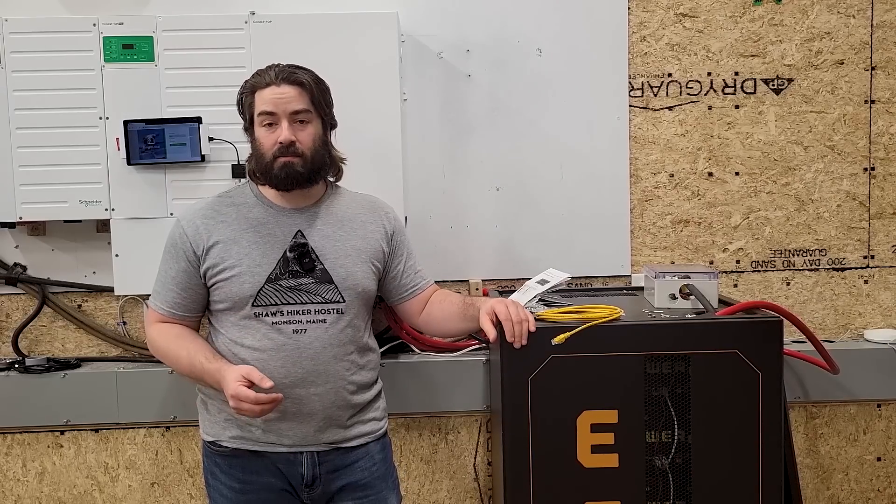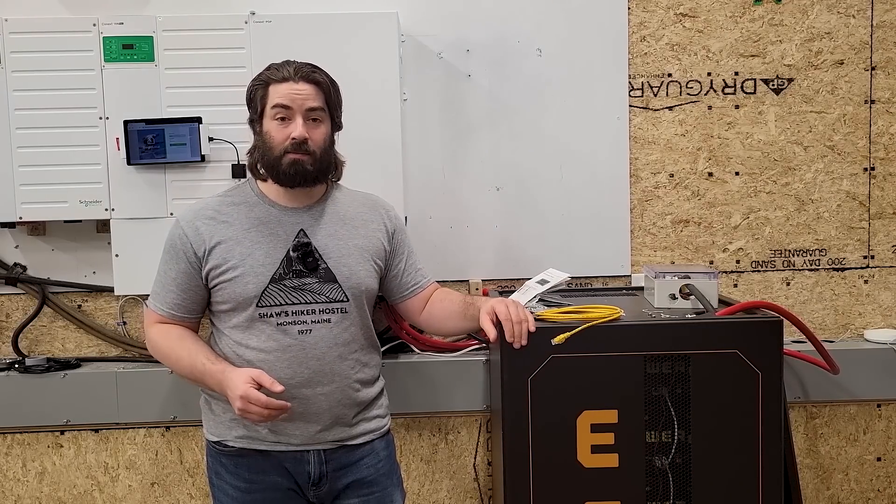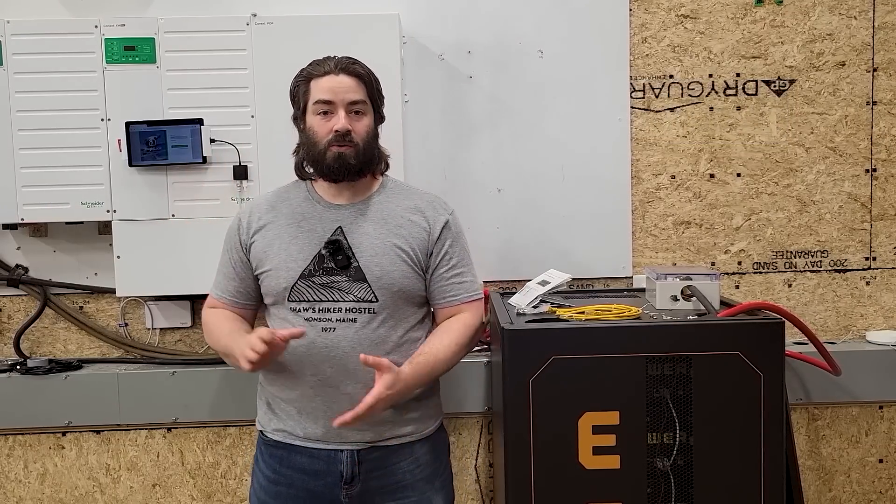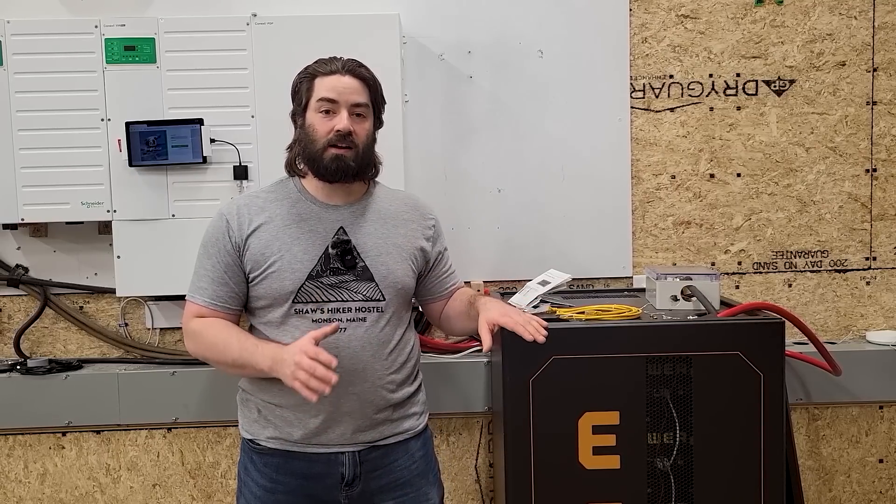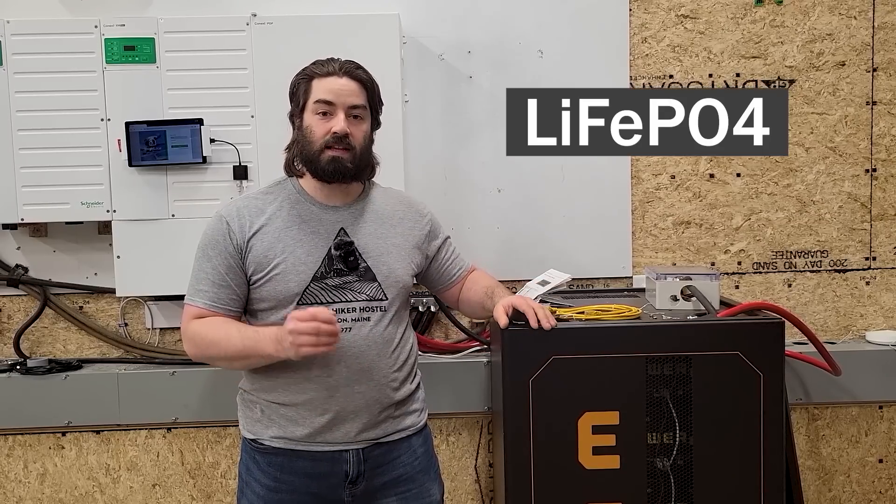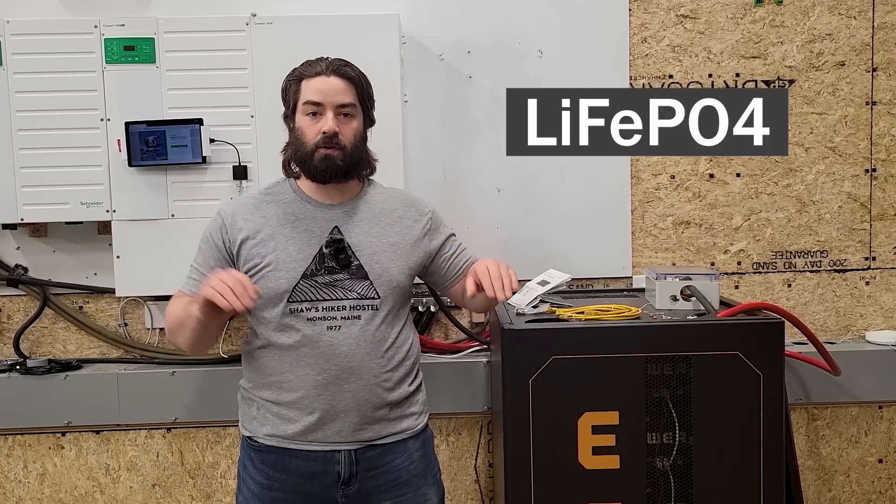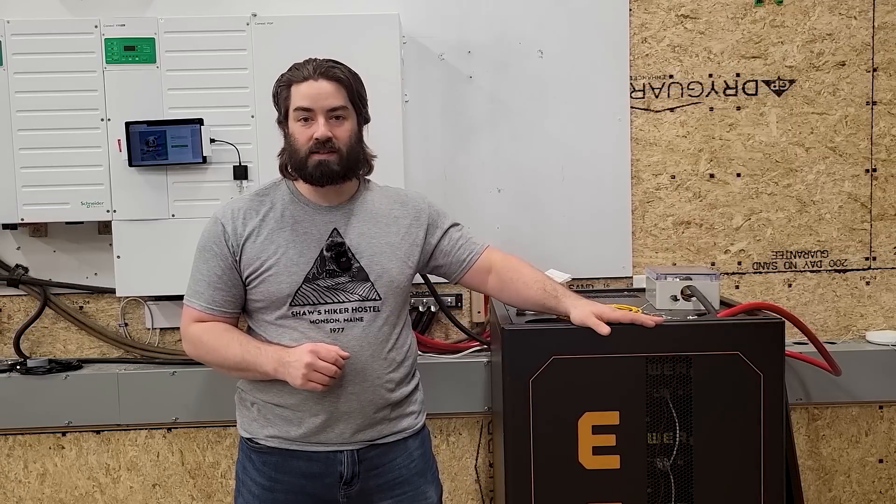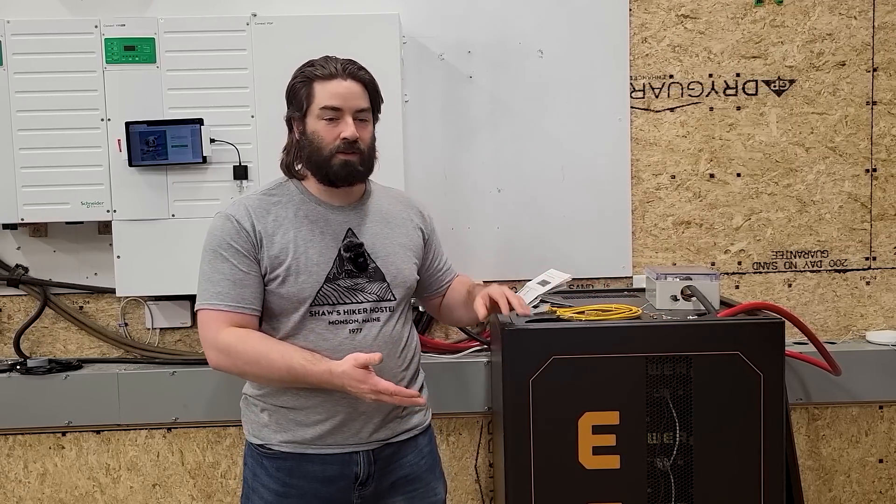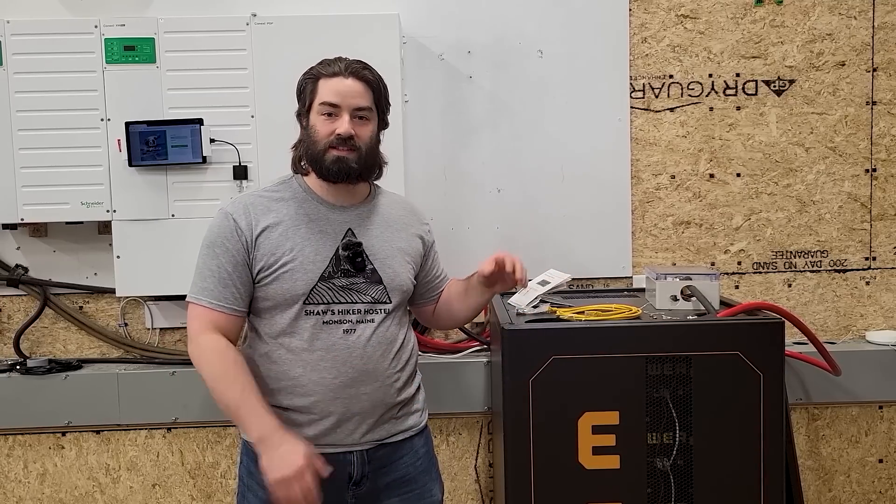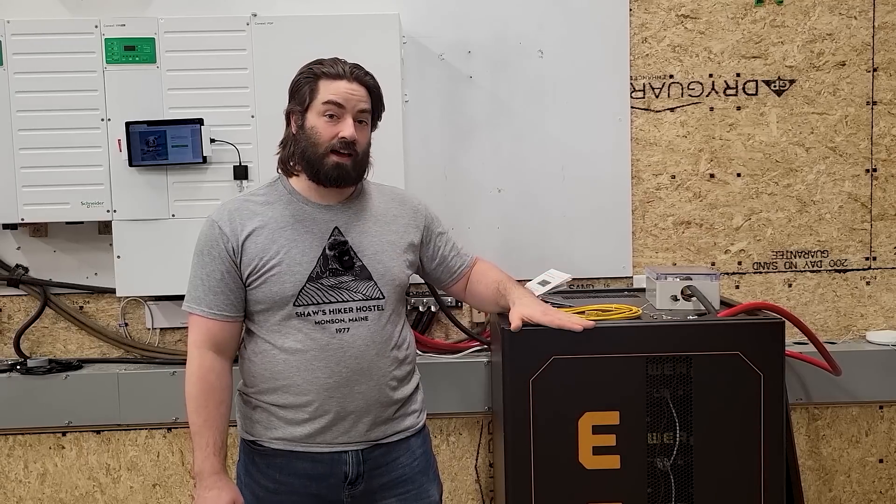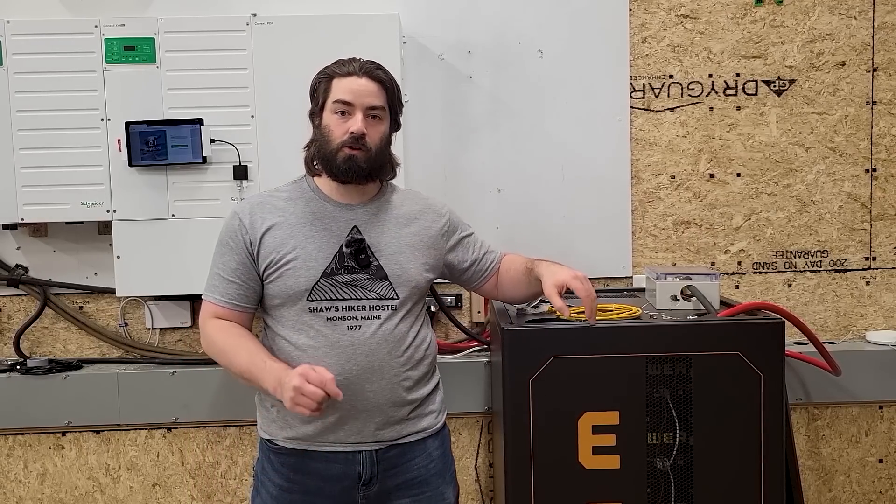Now that's just one example, and that's the main example that I have with my setup here. For the last few months, we've been running the entire property on this one Schneider inverter. It's been working really well. This is model XW Pro 6848. Currently, this inverter is only being able to see the voltage of the battery bank. It does not know the state of charge. Now this battery bank is lithium iron phosphate, which has a very flat voltage profile, meaning that it's almost always at 53 volts. And you don't know if it's at 90% state of charge or 20% state of charge. It's still somewhere in that 52, 53 volt range.